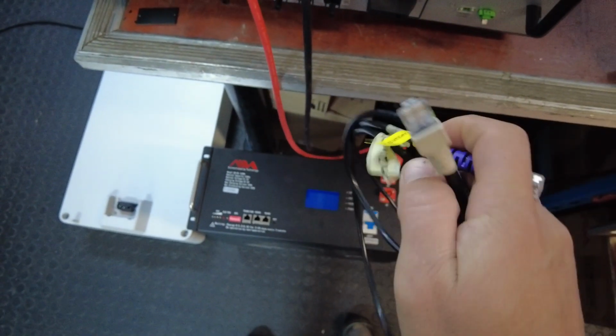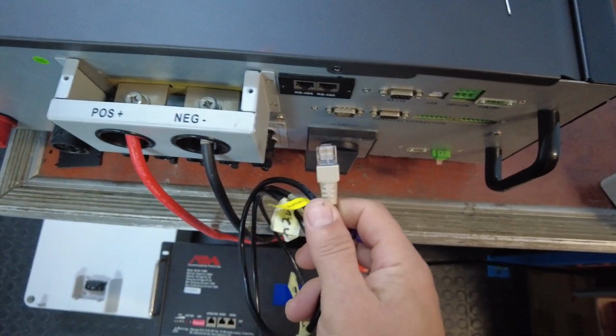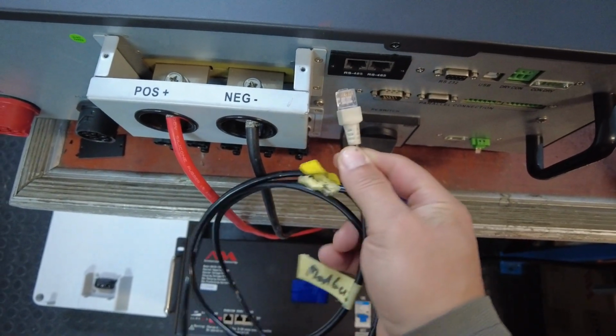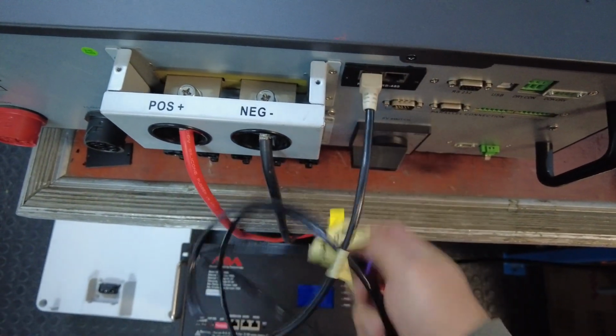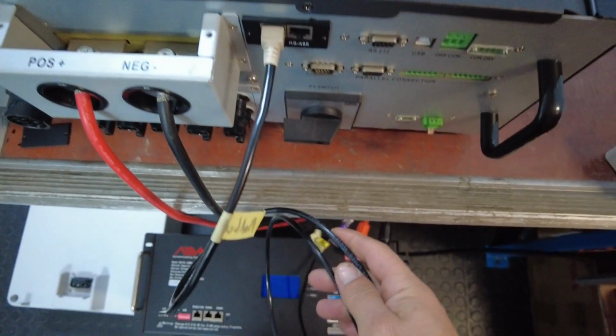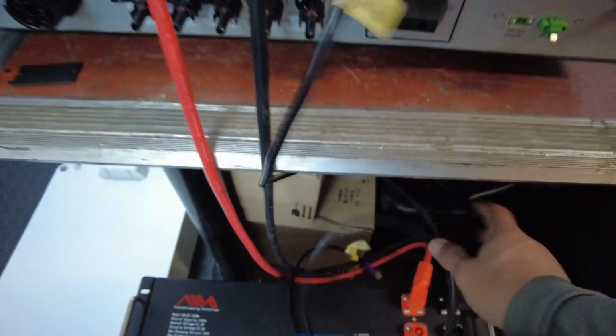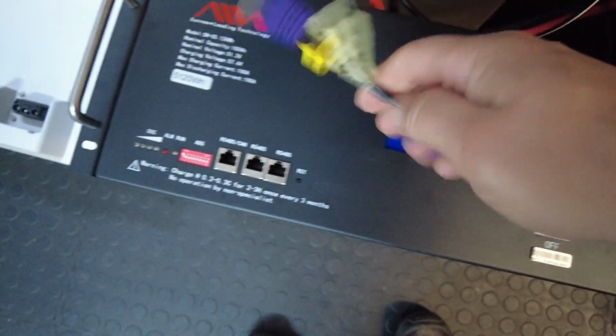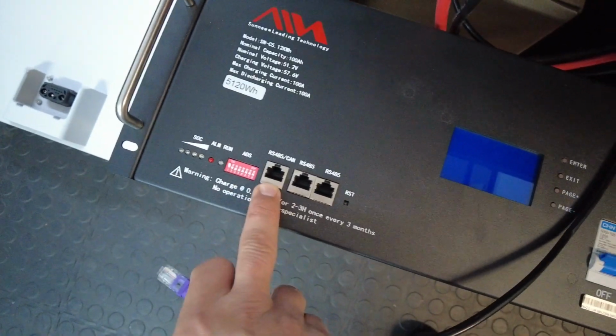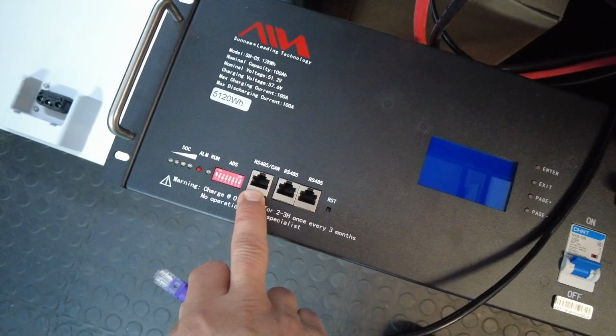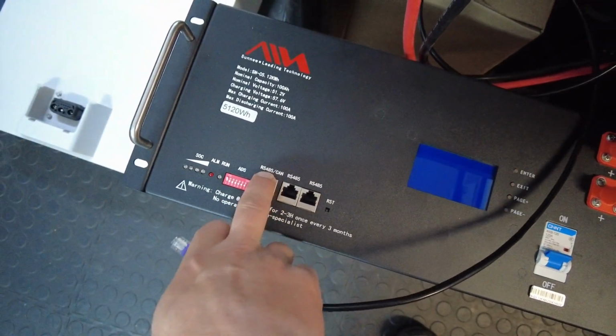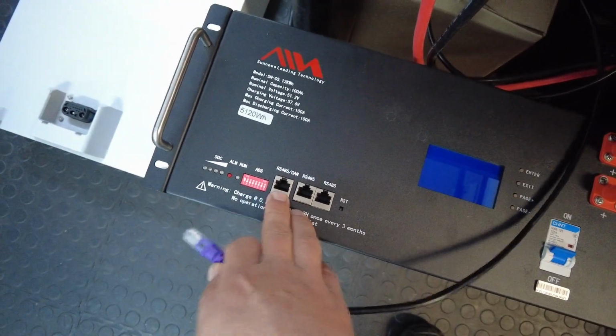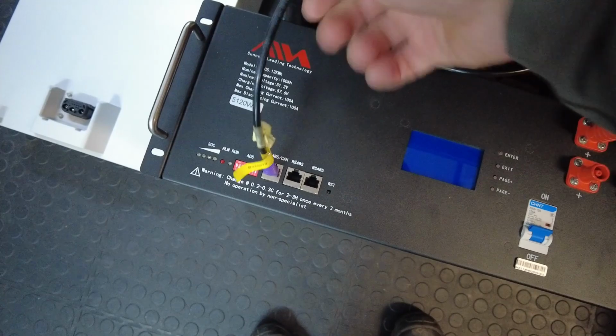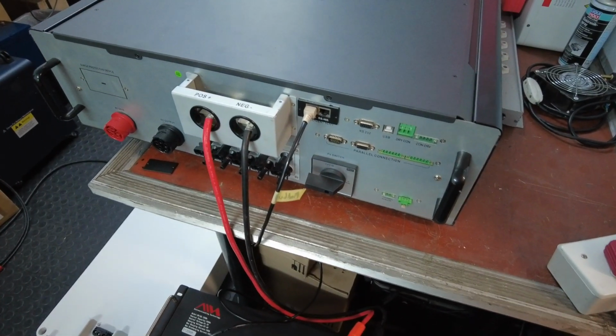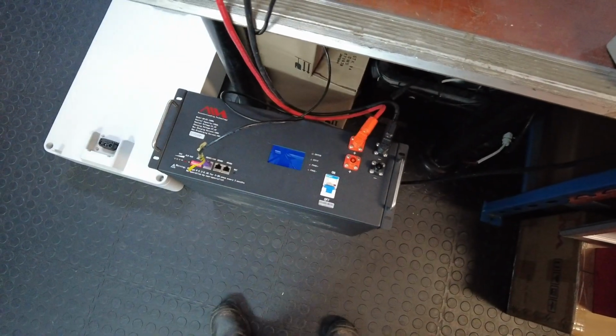Okay, let's connect the cable. On the inverter side, the Modbus card, the grey plug that I've crimped as shown before, you can connect to either one of these two RS485 ports. Doesn't matter which one of the two you use. And then on the battery side, you need to use this communications port that's standing on its own, marked as RS485 or CAN. We're basically using RS485 communication to the Modbus card to establish BMS communication. Okay, so the Modbus card is inserted, BMS communications cable is connected, DC cables are connected, we can start up.